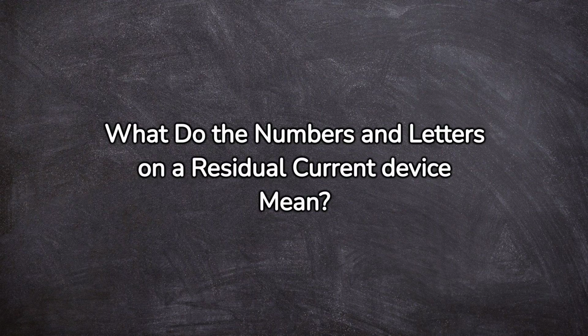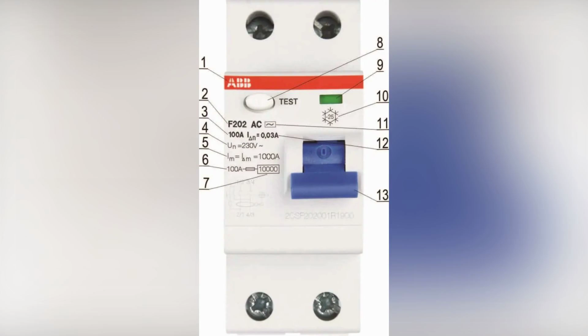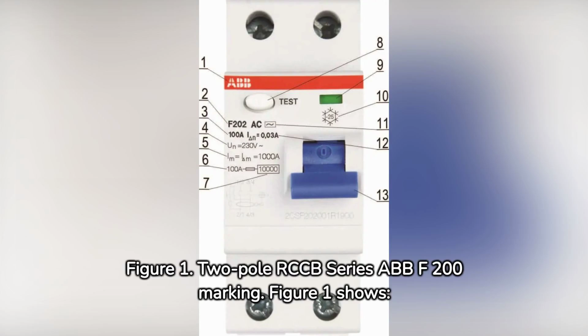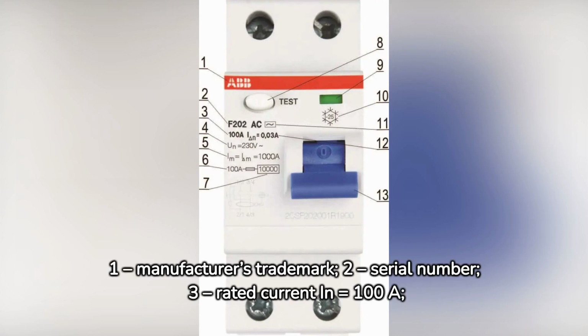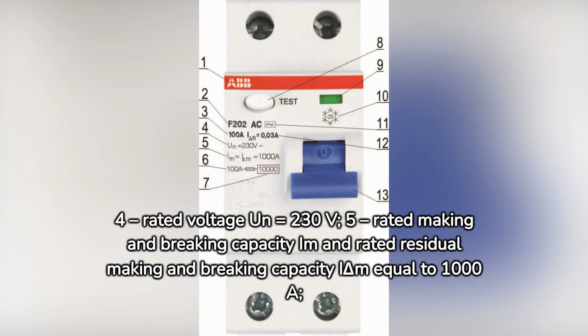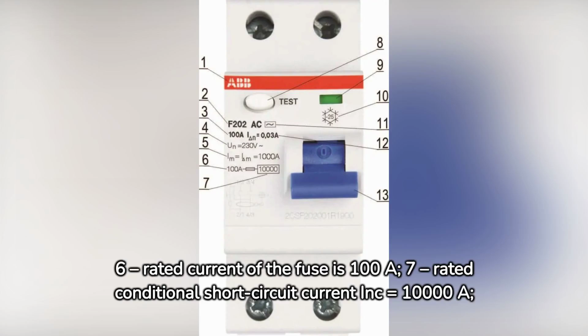What do the numbers and letters on a residual current device mean? For examples of RCD labeling, see below on screen. Figure 1. Two-pole RCCB series ABB-F200 marking. Figure 1 shows: 1. Manufacturer's trademark, 2. Serial number, 3. Rated current In equals 100A. 4. Rated voltage Un equals 230V. 5. Rated making and breaking capacity Im and rated residual making and breaking capacity IΔm equal to 1000A. 6. Rated current of the fuse is 100A. 7. Rated conditional short circuit current Inc equals 10,000A.